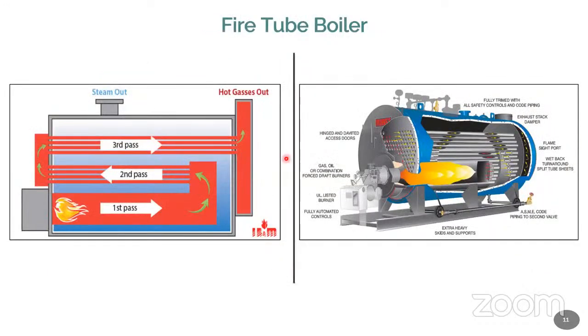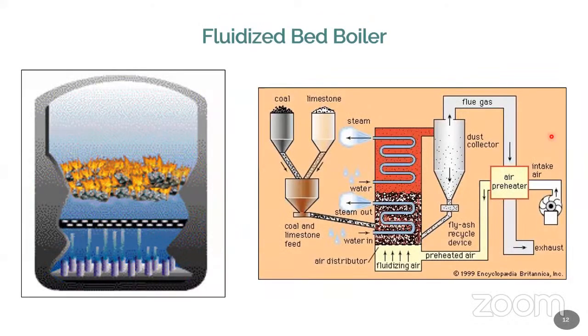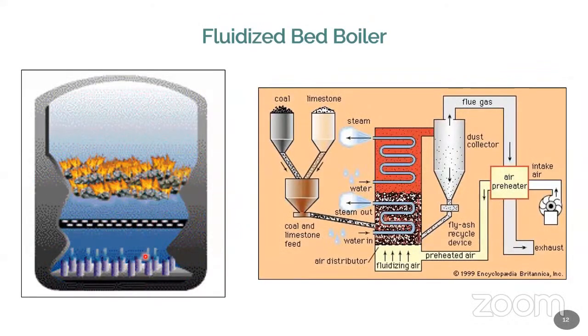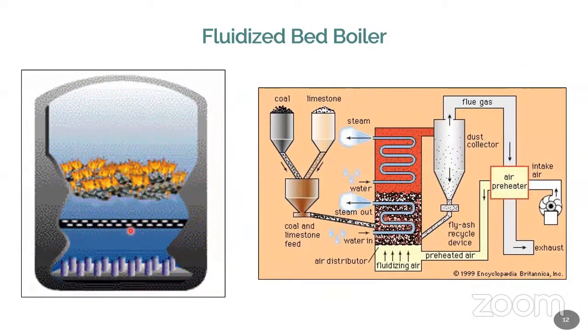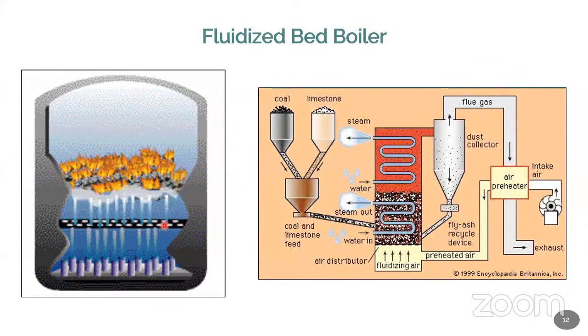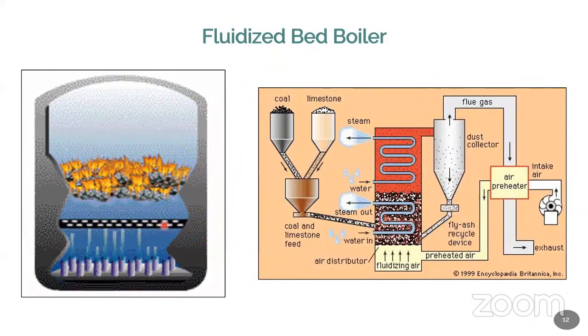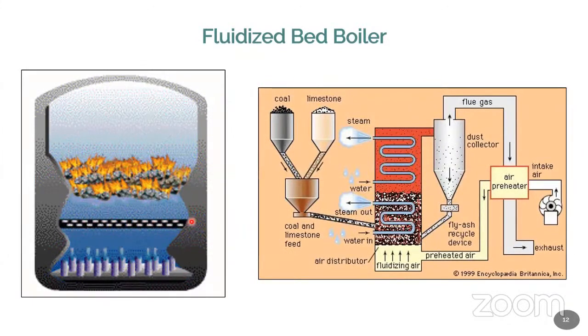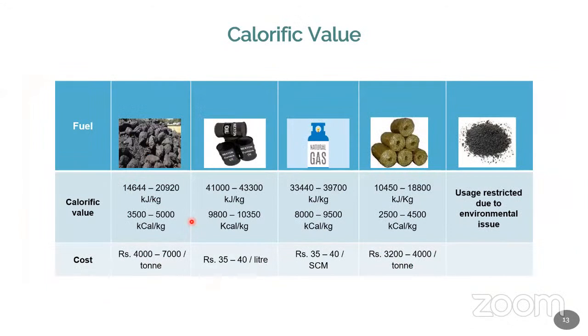Now this is the fire tube boiler, where your fire will be passing through the tubes, whereas on the outer side the water will be available, and gas will go out and steam will go out. This is the cross section or cut view of a fire tube boiler, where we are injecting the fire in the tubes, and they're surrounded by the water. This is the fluidized bed combustion, where water will be available. You have a bed, a fluidized bed, in which you are placing your fuel.